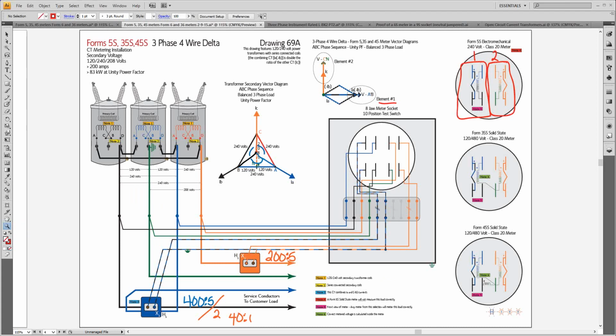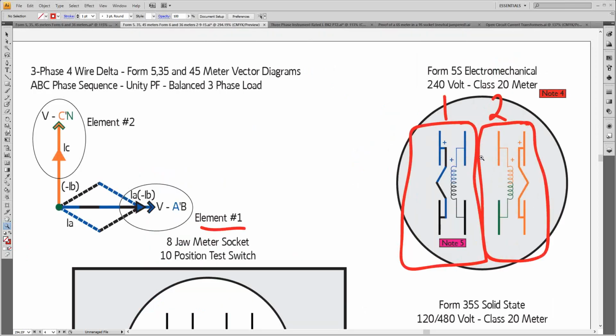So those unity power factor in a balanced system, right? Yeah, that's exactly what the vector diagram is: unity power factor and a balanced 3-phase load. So in my first element, I'm going to pick up from here, look at the vector diagram compared to what the metering is seeing. In the potential coil, in my first element here, on one side, I'm going to put A-phase voltage on my potential coil. On the other side of my potential coil, I'm going to put B-phase. And so across this first potential coil, I get A to B voltage. And that's this voltage right here, which is 240 volts in our system.